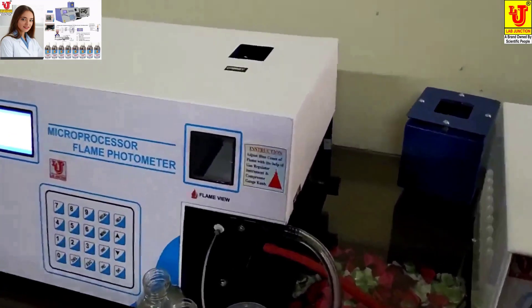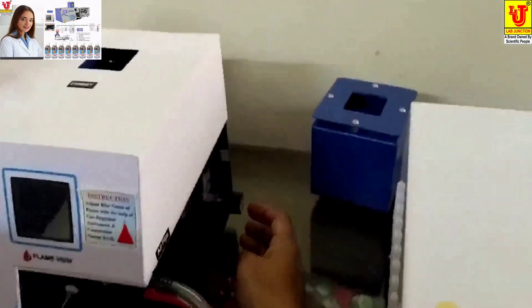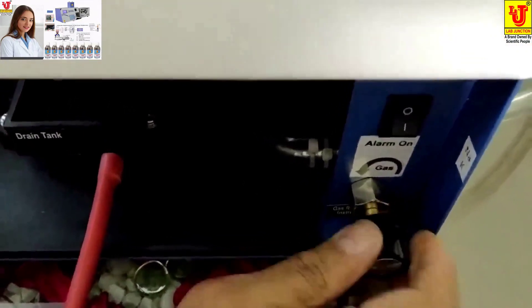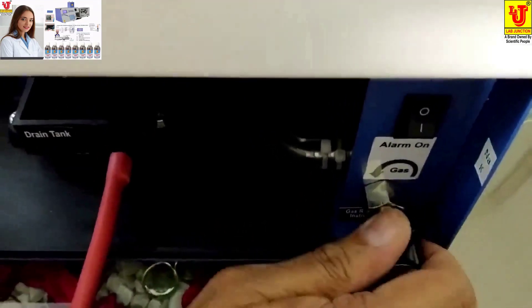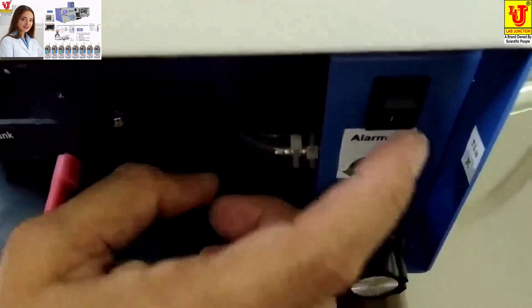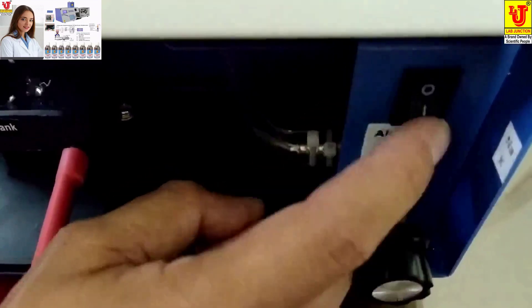Now, how to light the flame of the flame photometer. This is the gas regulator — first you minimize it. This is the minimize mark and this is the maximum. You have to minimize it. This is the alarm indication for gas. If gas is not present, it indicates a beep. You can take advantage of this by switching on this alarm.